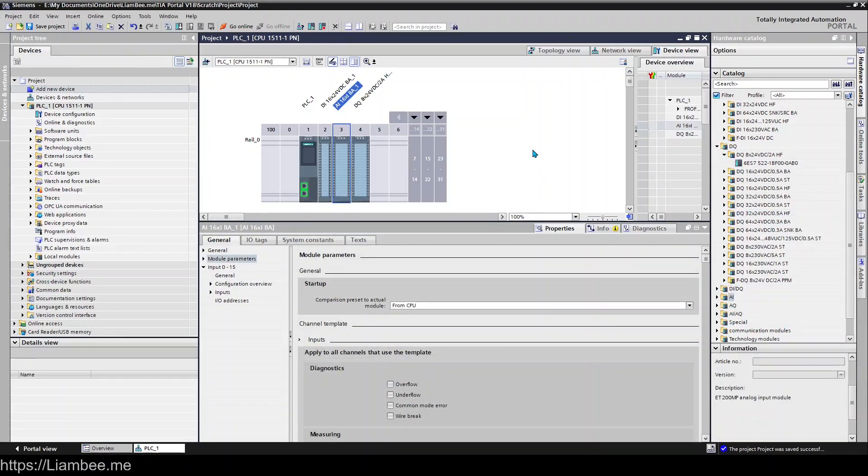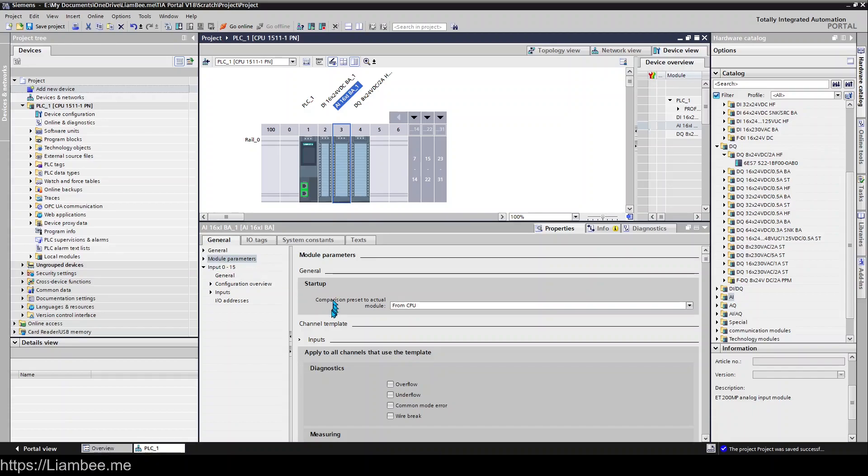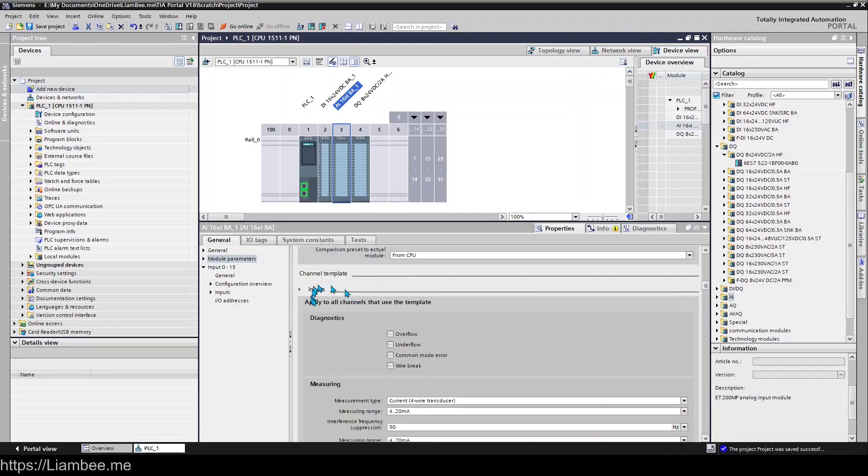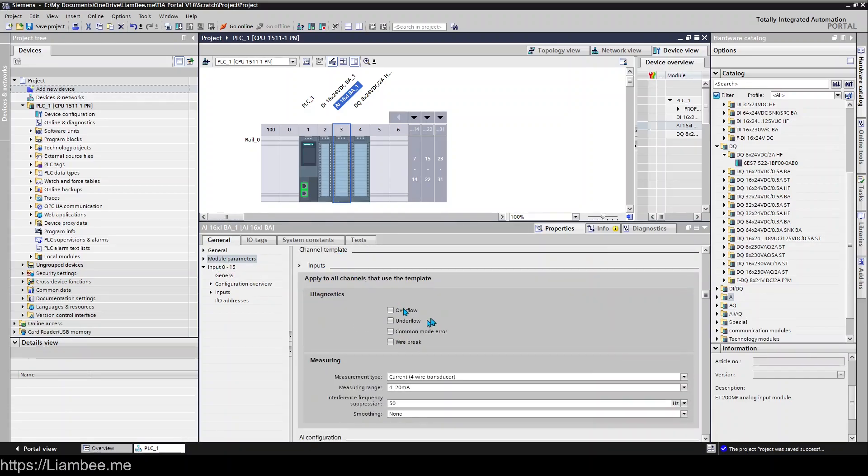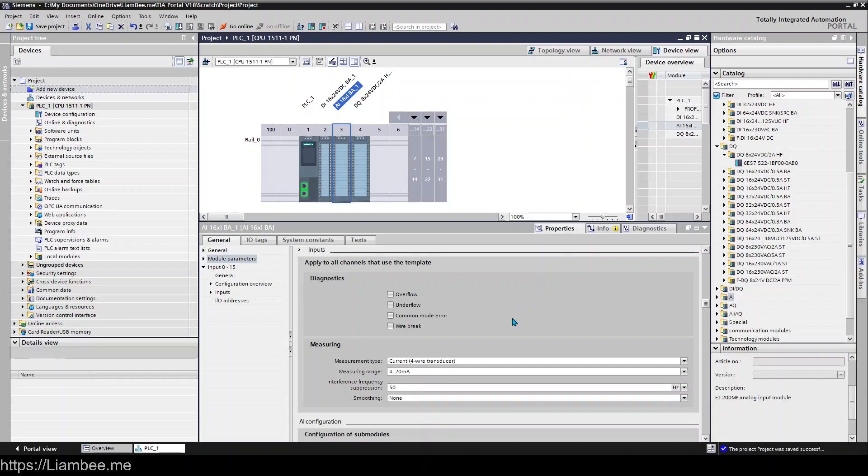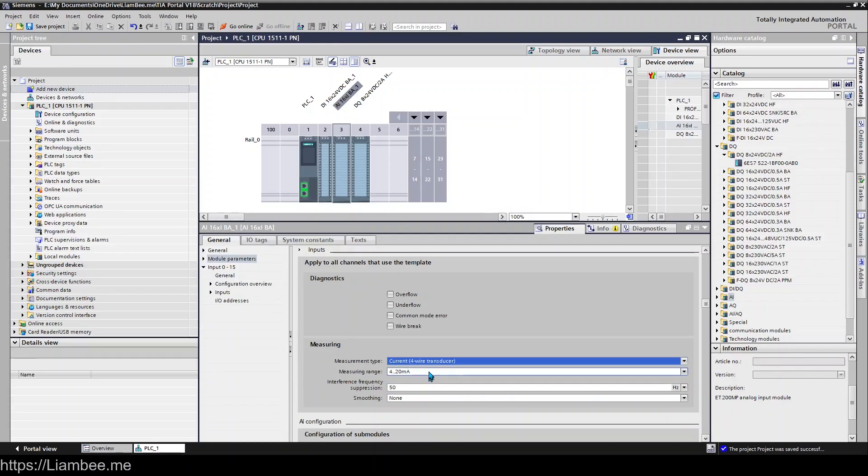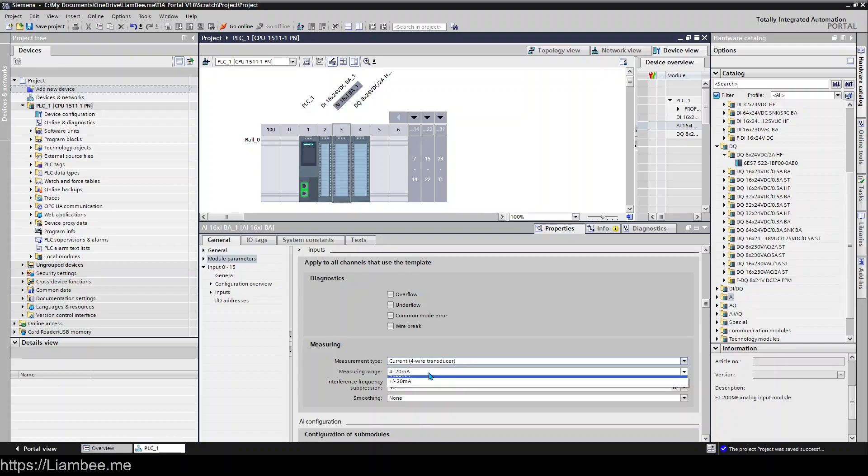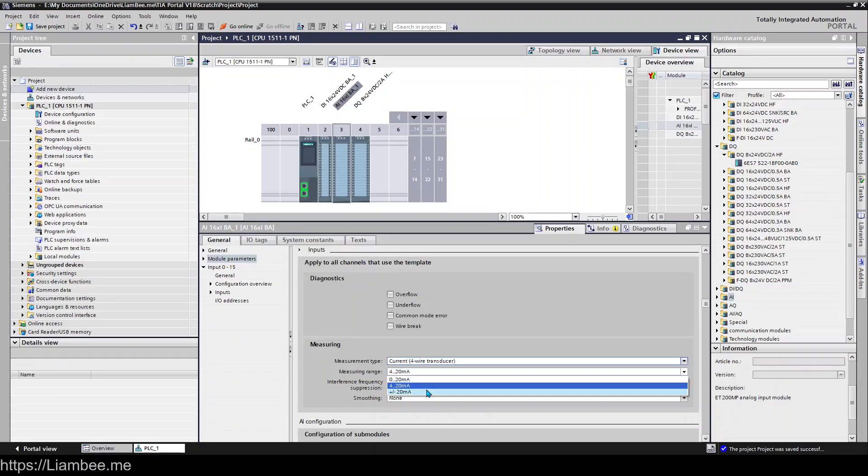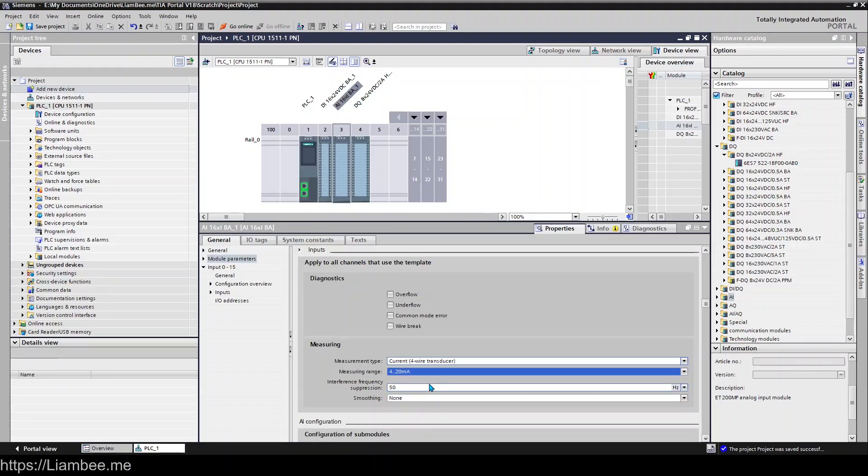Let's have a look at analog inputs and the configuration around those. Again, it's very similar. We have our module parameters, the startup configuration, a channel template where we can set overflow, underflow, wire breaks, various other things. But the key thing with analog cards is that you have the ability to change what your measurement type is. At the moment the default is 4-wire transducer, and on this particular card we can set 0 to 20, 4 to 20, or positive negative 20 milliamps as the range that we're detecting.